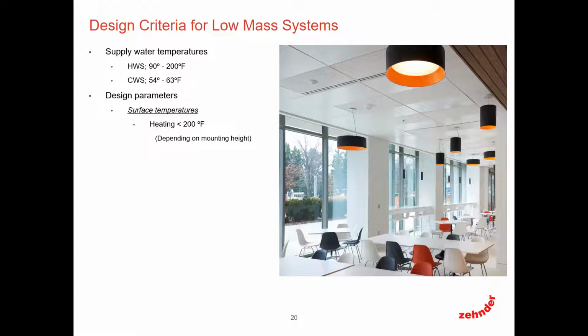I believe at a 9-foot mounted ceiling with 40% active coverage, you're looking at something like 140 degree water as your max, and that would not create a level of discomfort. So basically the intensity would be low enough that occupants wouldn't feel that hot head. On the cooling side, generally we're looking for somewhere around 62 degrees on the colder side. And what do those numbers, those surface temperatures, correlate to? They're very important to us as designers because they correlate to BTUs per square foot.